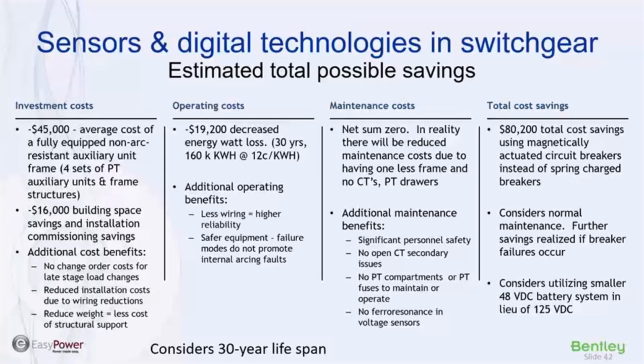The sensors typically have much less power consumption than instrument transformers. In fact, it is actually significant. So you would save operating costs there, right? And in terms of actual maintenance, that's neutral, but you do get significant safety advantages in using sensors, right? So you avoid problems like high voltages due to open CT secondaries. You avoid ferroresonance. So a lot of issues are avoided when using these technologies, right?